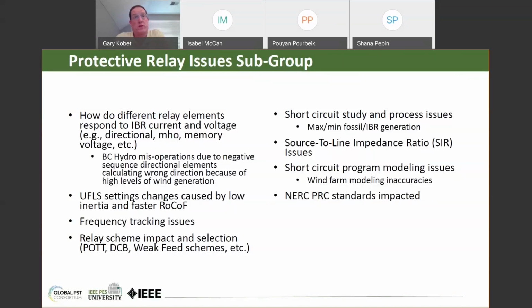We're going to discuss how the paper covers how different relay elements respond to IBR current and voltage, where the nature of the response is different than conventional synchronous machines. There have been misoperations of negative sequence elements, of negative sequence directional elements, that are documented, and the paper provides references to those. I'll discuss a little bit about that in just a second. Under frequency load shedding and the effect of lower system inertia and faster rate of change of frequency. That's an issue. Frequency tracking issues. Relay scheme impact, the paper goes through a little bit of detail on that, and some follow-up work by some Power System Relay Committee working groups that have completed their work recently go into that a little bit more.